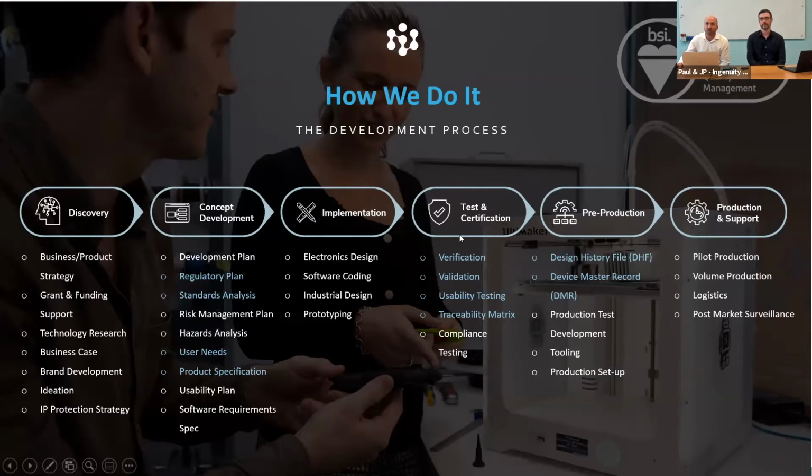But this whole process is governed by quality standards. You'll notice up in the right-hand side here, 13485. It's important, it's essential that you're certified, that this design process is certified to 13485. And what it's concerned about is the quality of the management process that governs this design process. Document control, revision control, making sure that documents don't have mistakes, that they're not incorrectly used, ensuring that they're properly design reviewed, ensuring that there's traceability, that requirements are carried through, validated.